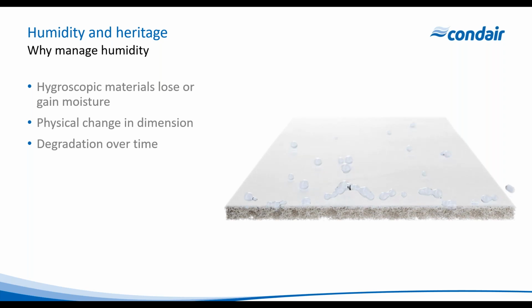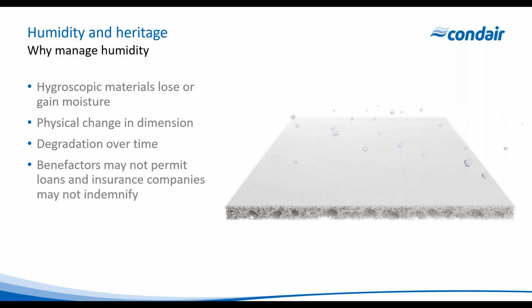Even small swings can change the material, and expansion and contraction over time can have a cumulative effect on objects and artifacts, depending on the material involved. And benefactors may not permit loans, and insurance companies may not insure, say, travelling exhibitions. In fact, it's very common for an insurance company to request that the temperature and the relative humidity in the potential gallery space has been stable for 3 months before they accept that exhibition, so that they can guarantee that the climatic conditions within the gallery space are not going to affect the materials.